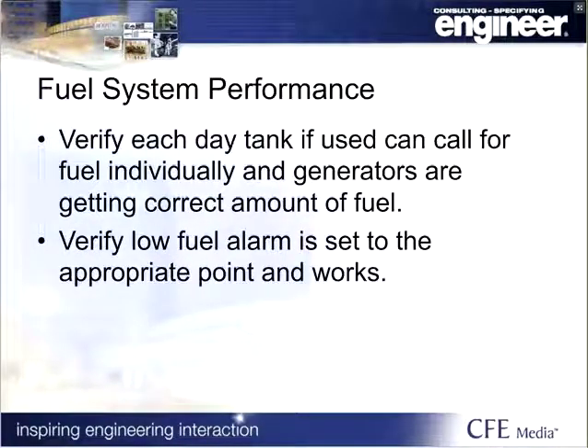As part of the system, we also need to look at the fuel. The fuel obviously keeps the system running. It's a very important feature. We need to make sure each day tank is going to call for the fuel, and that the level float switches and the way the system is designed to run actually works.